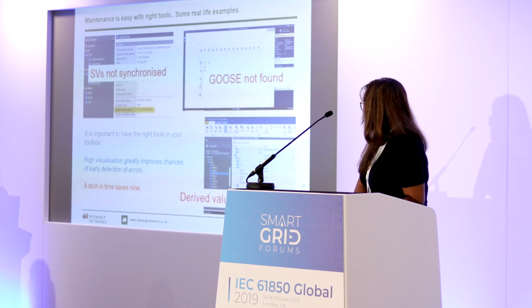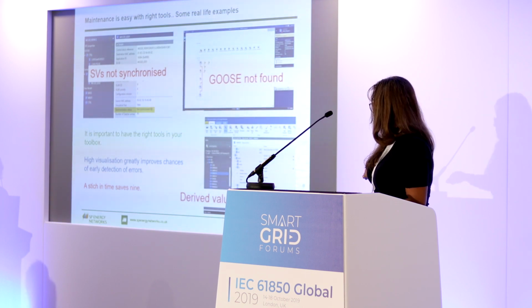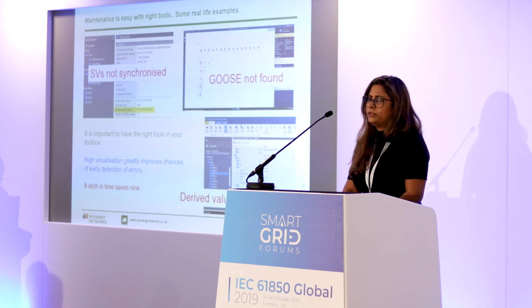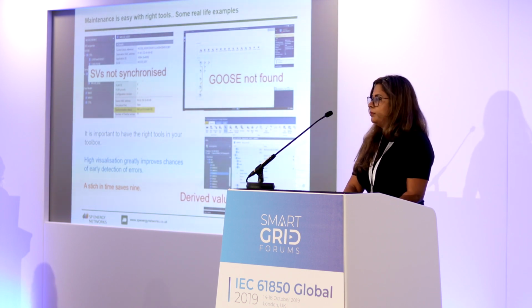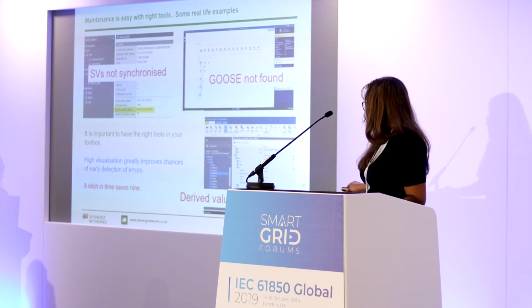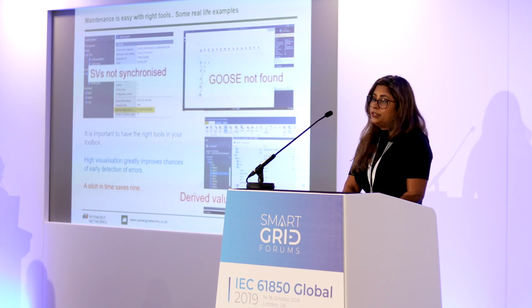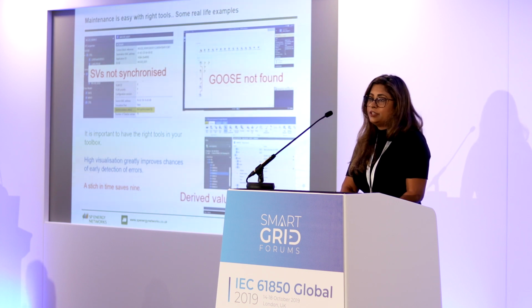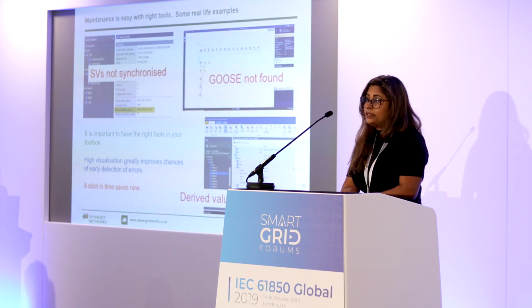Here are some examples - the last one is very important. Sometimes you have questionable data with nothing actually alarming or showing up, but it might point to a more underlying problem. In one case, the issue was an unshielded Ethernet cable used in a high voltage substation, and the sample values had CRC errors in them. It took us a long time to find out what the issue was. But having questionable data visible on the system, without needing to drill down much, gave us the indication that something was wrong and needed to be fixed.